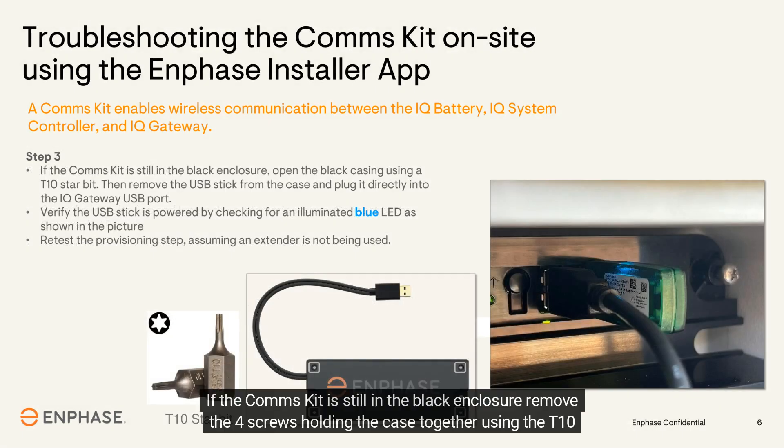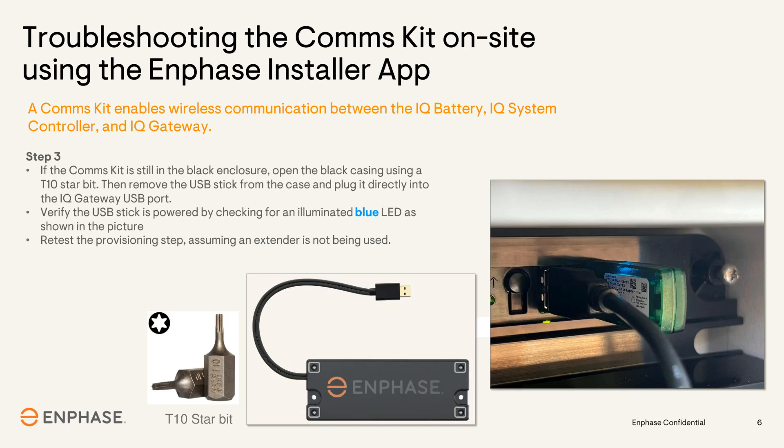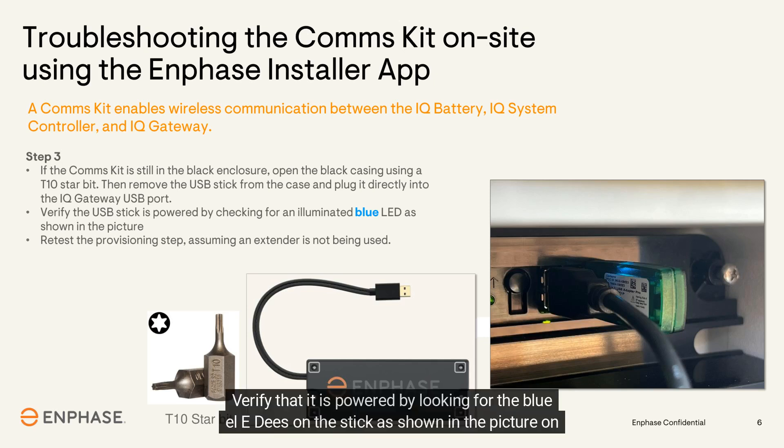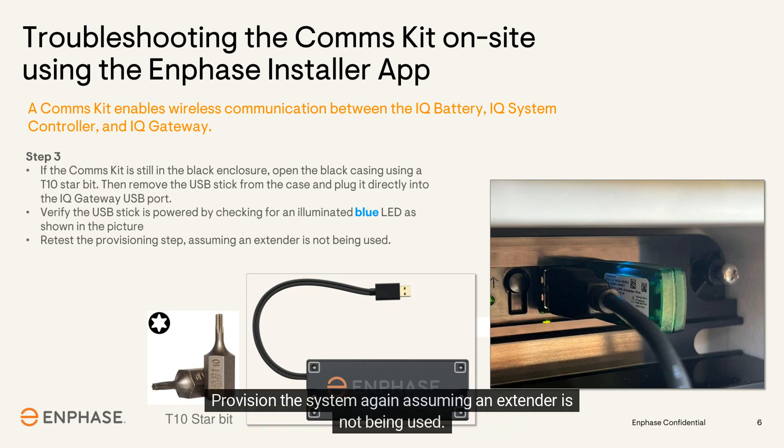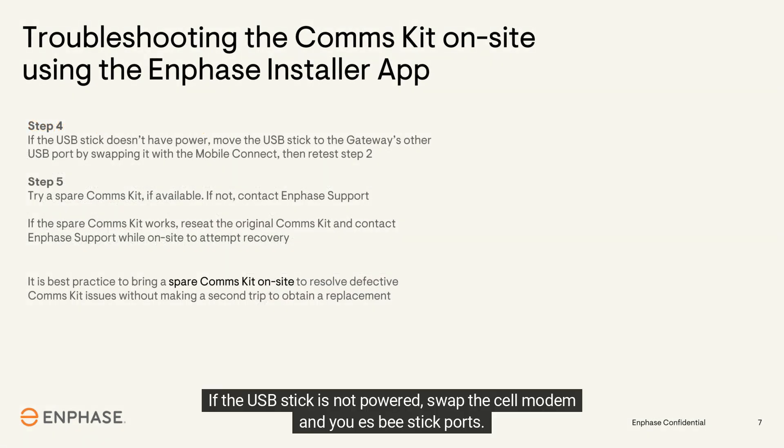If the comms kit is still in the black enclosure, remove the four screws holding the case together using the T10 star bit, then remove the USB stick from the case. Plug the USB stick directly back into the gateway and verify it is powered by looking for the blue LEDs on the stick, as shown in the picture. Provision the system again, assuming an extender is not being used. If the USB stick is not powered, swap the cell modem and USB stick ports.